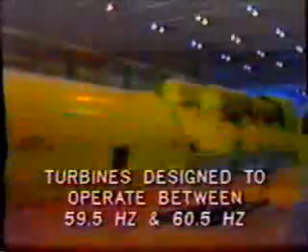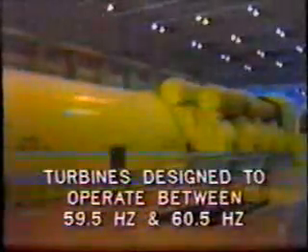As the generator is synchronized to the power system, it is responsive to disturbances which occur on the system. In some cases, this can prove to be hazardous for the generator or its prime mover. One typical example is that of frequency. Large steam turbines are designed to operate within a very narrow range of speed. That is, with the frequency between 59.5 and 60.5 hertz.